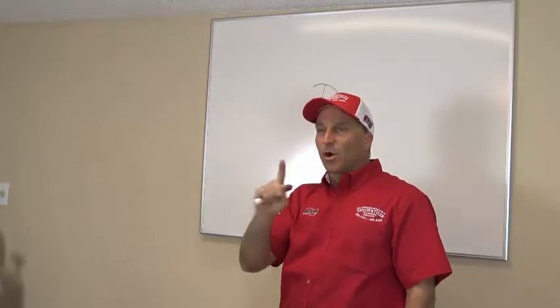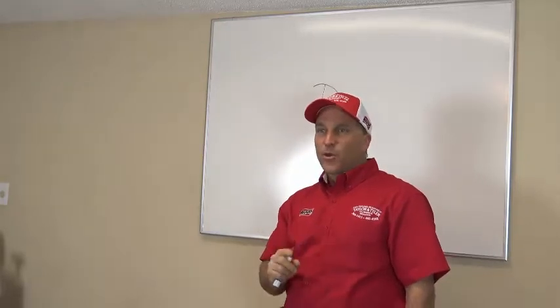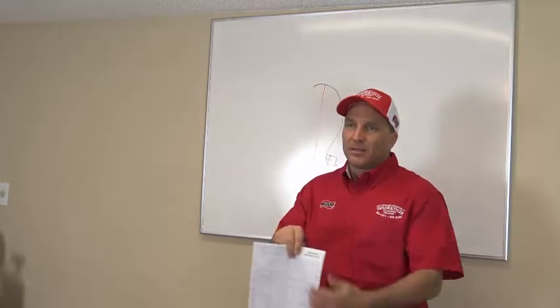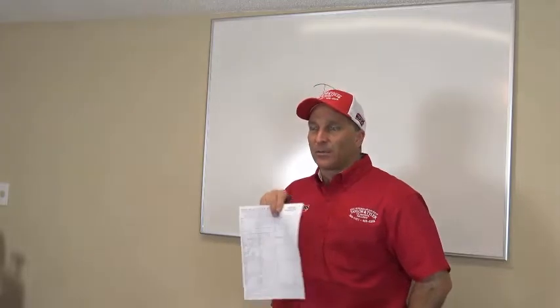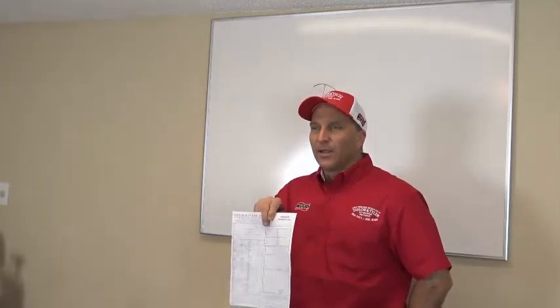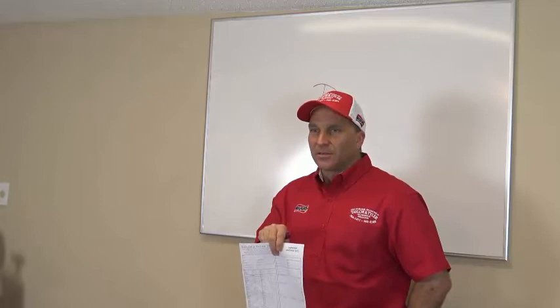You can't just look at one thing. You can't just say, hey, there you go. Eric told me subcooling should be 12 degrees. It's 18. I'm letting refrigerant out. I'm getting it to 12. I'm sorry, I'm recovering the refrigerant, and I'm getting it down to 12 degrees.